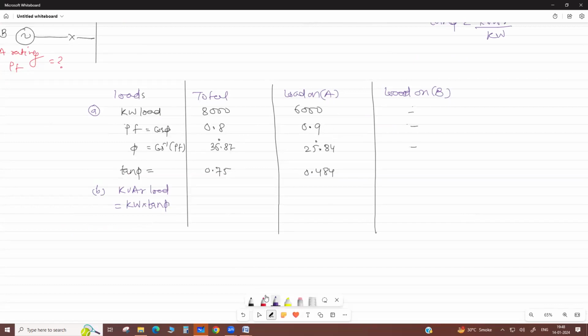So what is the total reactive load here? This is total, which will be divided between both. So if you subtract this - load on B equals total minus shared by A, total minus load on A. So the kilowatt we calculate easily: 8,000 minus 6,000 gives you 2,000 kilowatt active load. And now we calculate their reactive power - what is the reactive load?